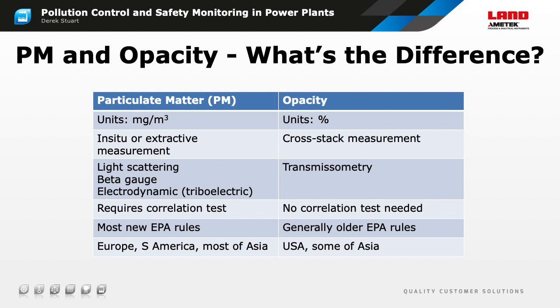Because particulate matter and opacity measurements are essentially 2 ways of looking at the same thing, it's important to understand the differences. A PM monitor measures in units of milligrams per cubic meter, whereas an opacity monitor measures percent opacity. A PM monitor can use a variety of different measuring techniques, including some which are not based on optical properties of the particles. An opacity monitor is, by definition, measuring transmission, so it has to use a transmissometer. A PM monitor requires a correlation test, so it can relate the measured parameter, light scattering or whatever, to the dust concentration. An opacity monitor leaves the factory fully calibrated and does not need further calibration, though it is generally necessary to verify the linearity of an opacity monitor using traceable, neutral density optical filters.